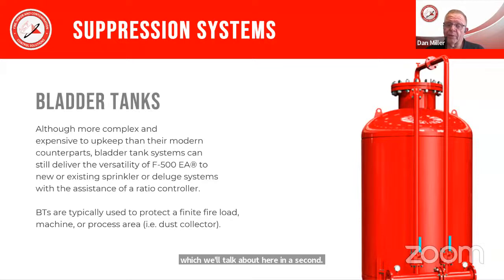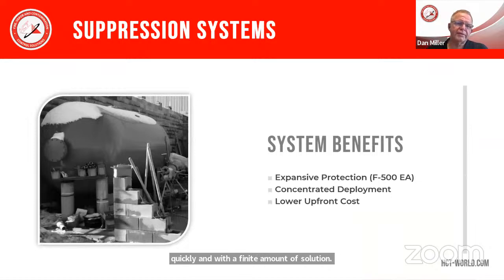Now, our bladder tank systems that we provide and we commission and we engineer are typically used to protect a finite fire load, something like a machine or a process area, something like a dust collector, where we know we can overcome that fire situation because of its relatively limited size very quickly and with a finite amount of solution. System benefits behind a bladder tank system are that even though it may be limited to a certain quantity, because it's much more effective at cooling and extinguishing than plain water, we can put that fire out with quite a bit less overall solution than plain water. It's a concentrated deployment and lower upfront cost typically.